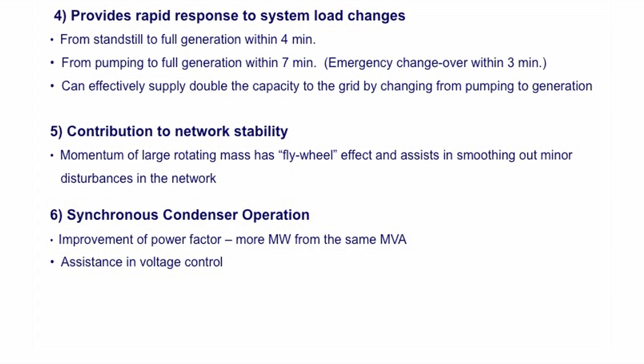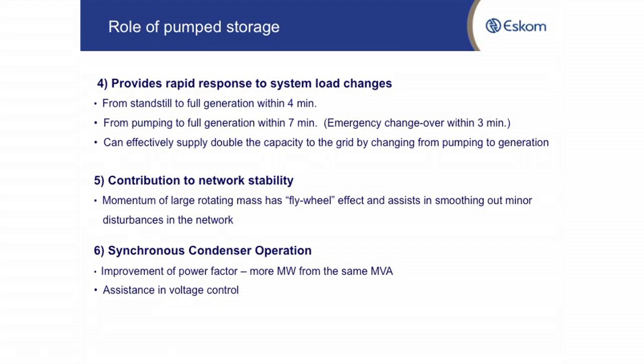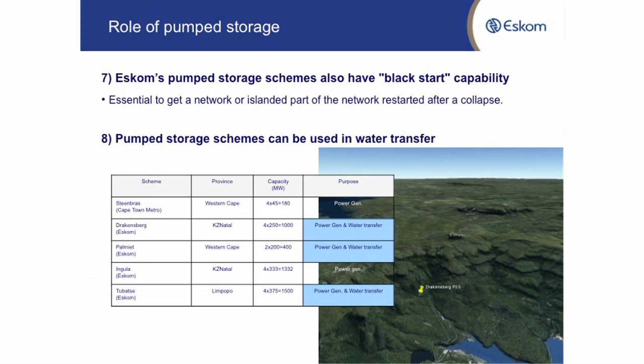Contribution to the network stability: it has a very large runner and very high rotating masses, so the inertia is very high, and any fluctuation on the grid can be accommodated by that high rotating mass. And then there's another one, synchronous condenser operation. During pumping and during generation, you can actually rectify the power factor on the grid by playing with the induction of your electrical motor. We also have black start capabilities at each pump storage. Should we have any blackouts, you can power up the grid again from pump storage.